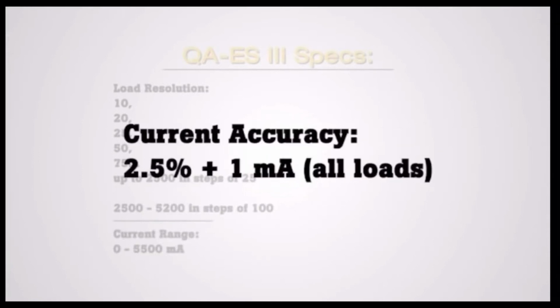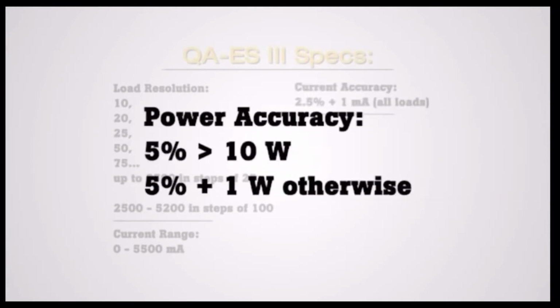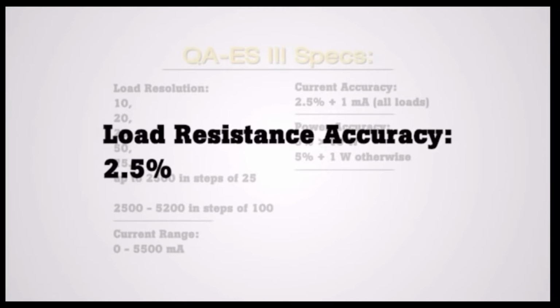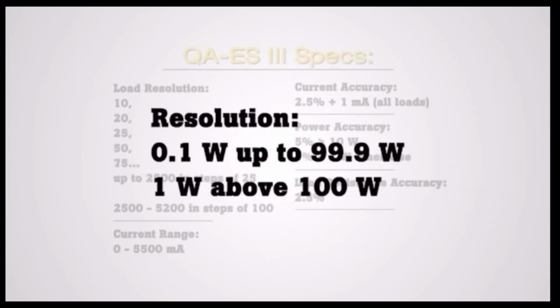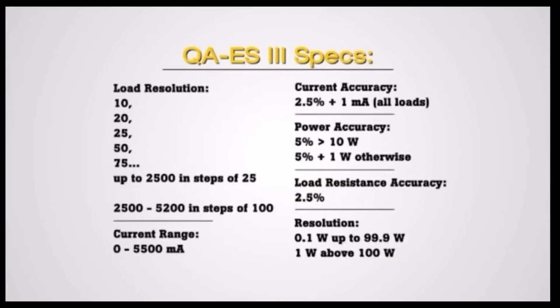Plus, it's twice as accurate with current accuracy of 2.5% of reading plus 1 milliamp for all loads. It's exceptionally accurate with generator output power accuracy of 5% greater than 10 watts and 5% plus 1 watt otherwise. In addition, it provides a load resistance accuracy of 2.5%. The QA-ES3 is also highly precise with a tenth of a watt resolution up to 99.9 watts and 1 watt above 100 watts for power measurement.